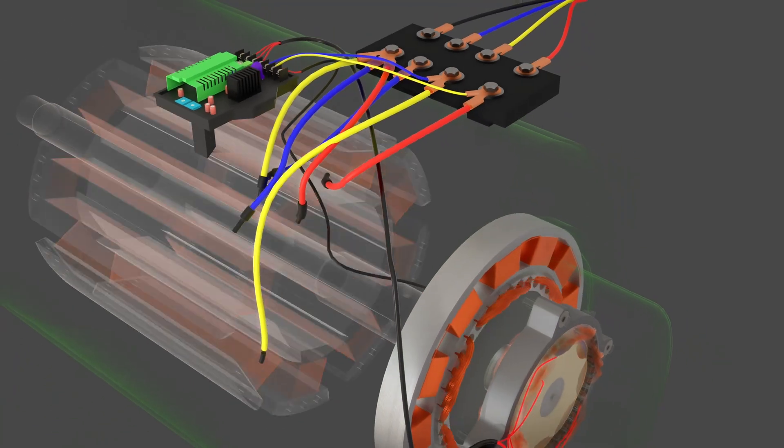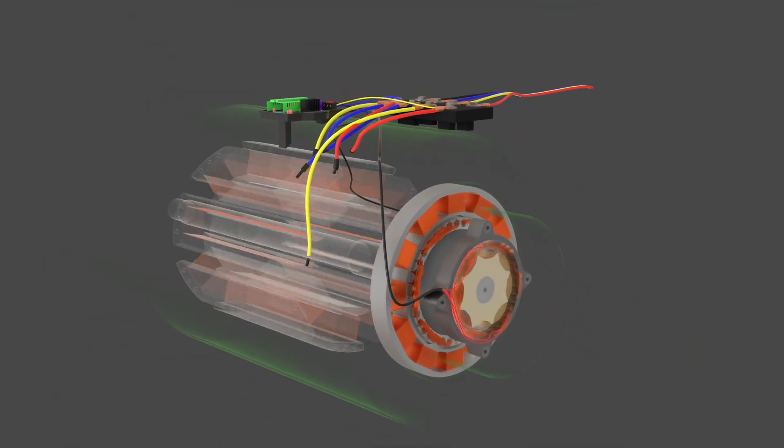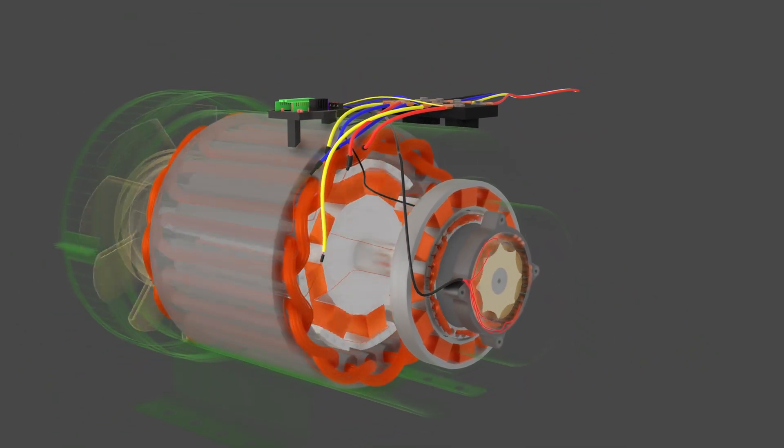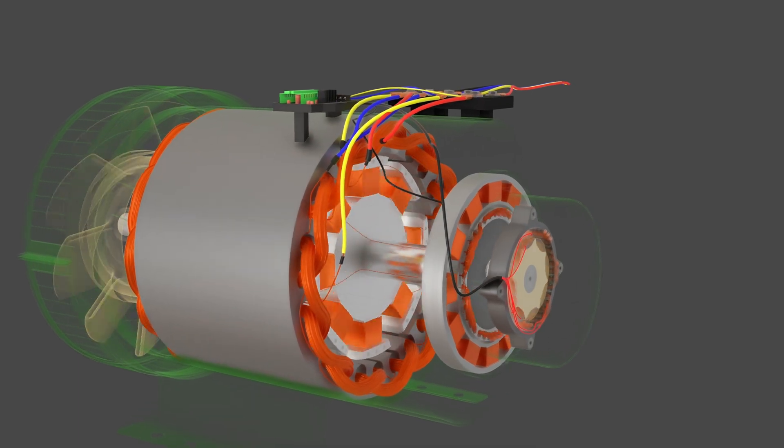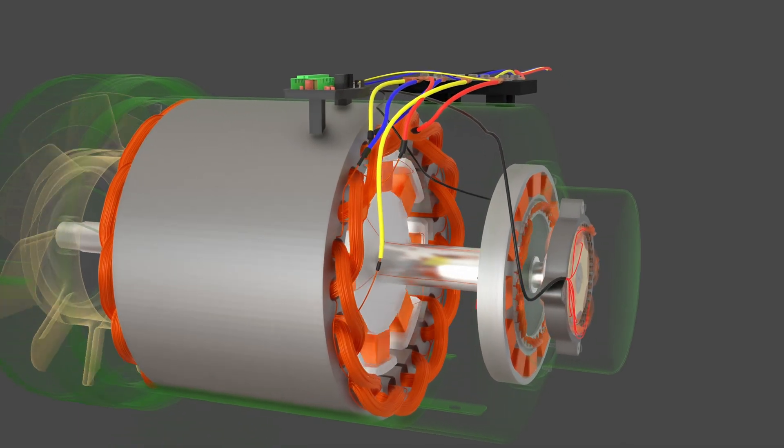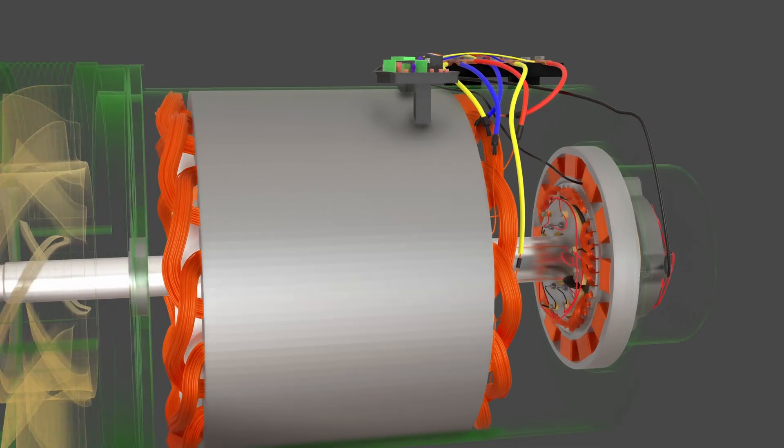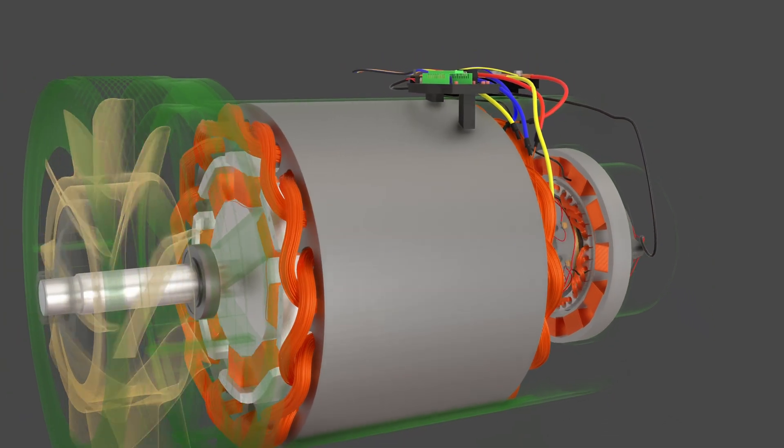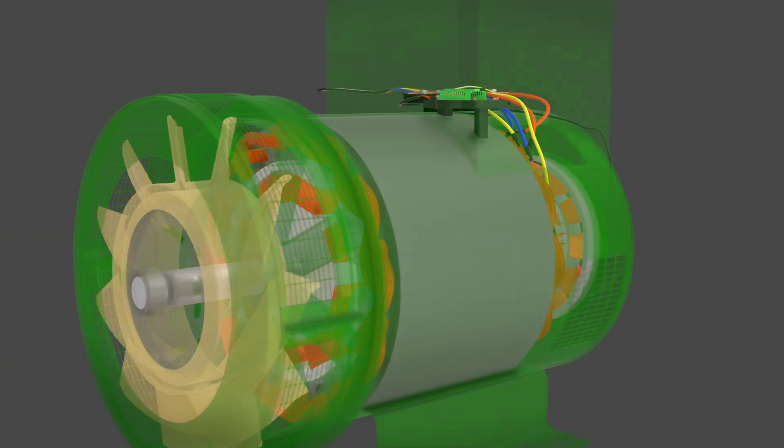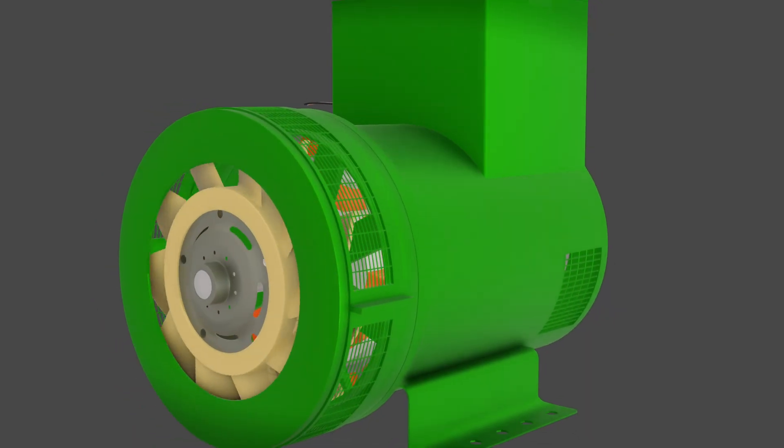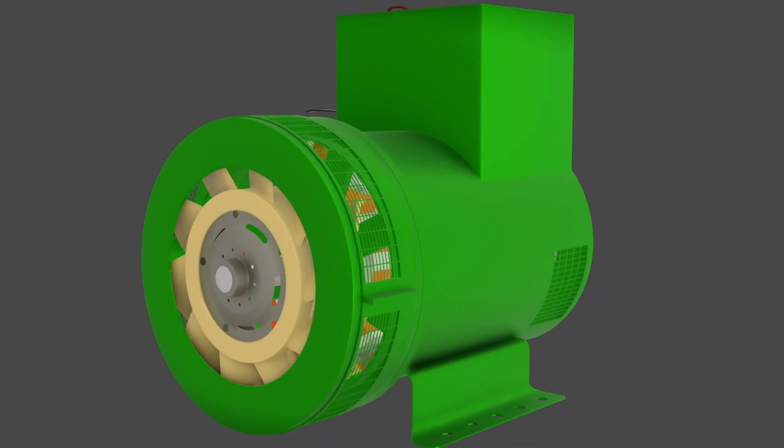The brushless excitation system with PMG provides several advantages: constant power supply to the AVR regardless of load conditions, no residual magnetism dependency for startup, faster voltage recovery during load transients, and elimination of carbon brushes for maintenance-free operation. If you found this video helpful, give it a like and don't forget to subscribe.